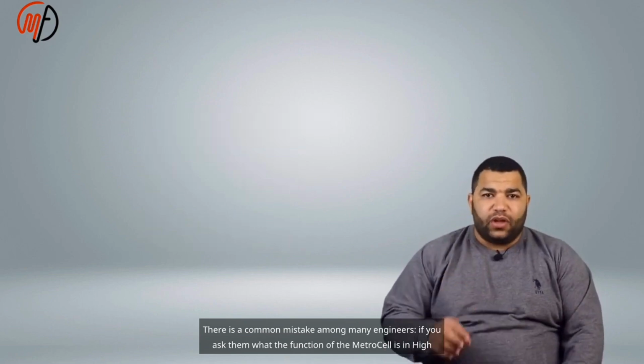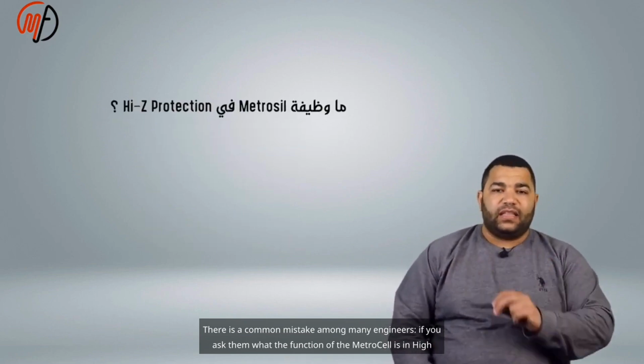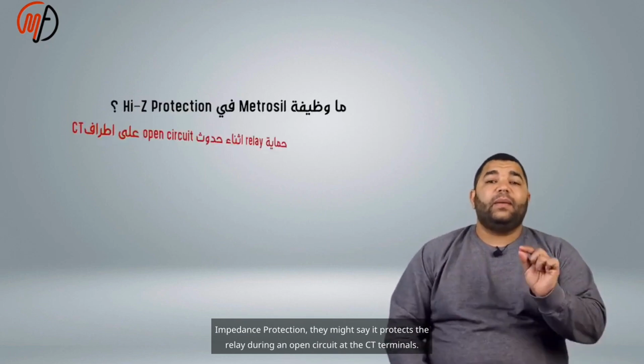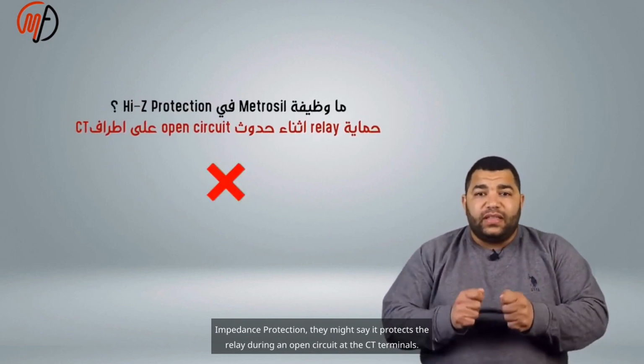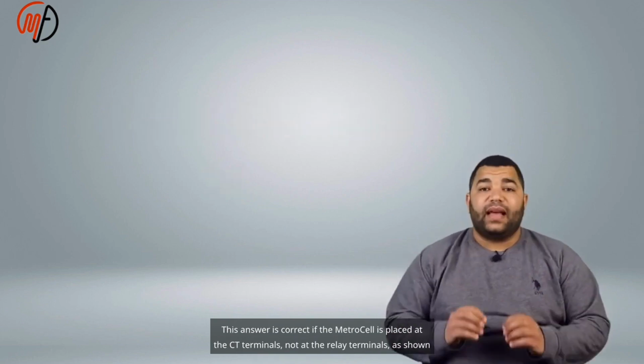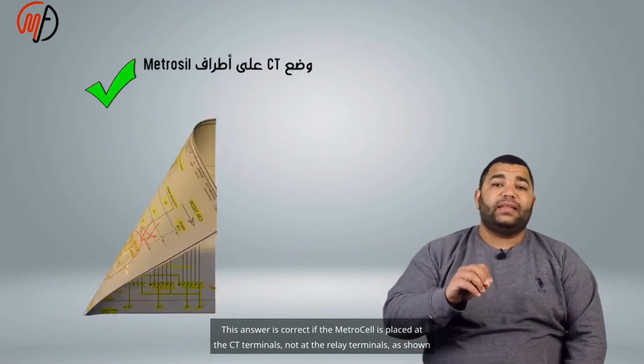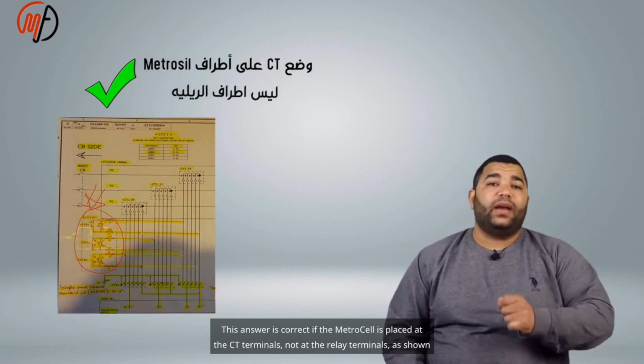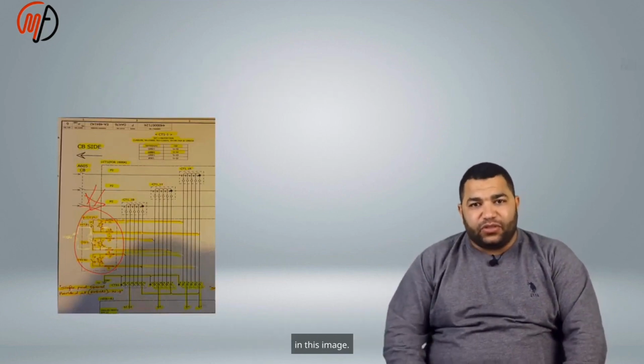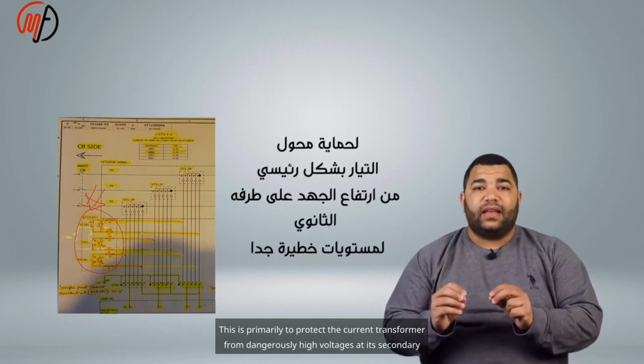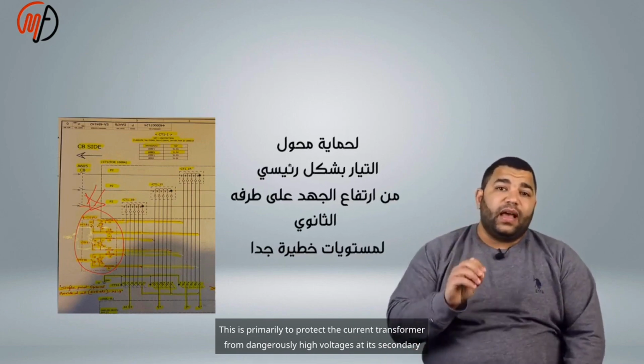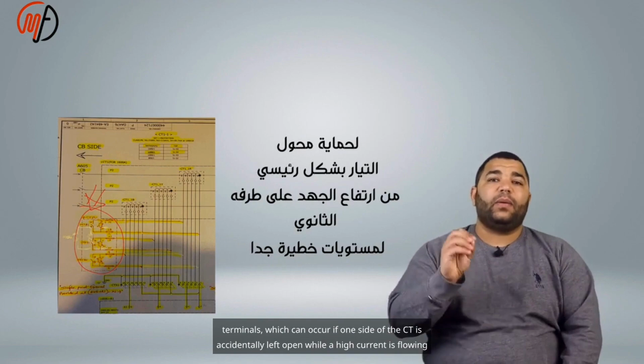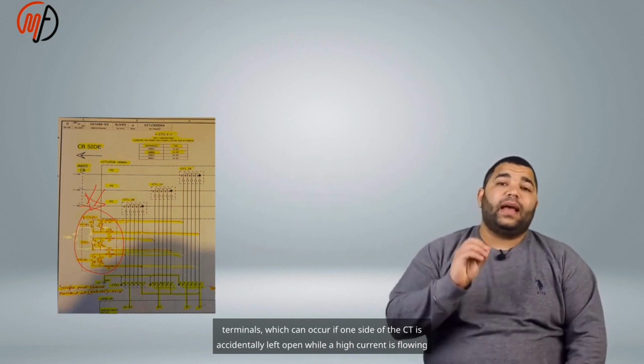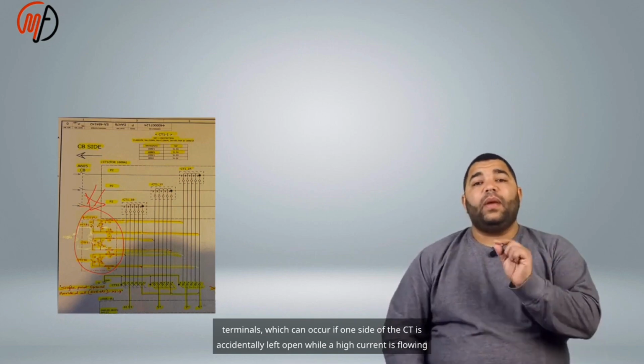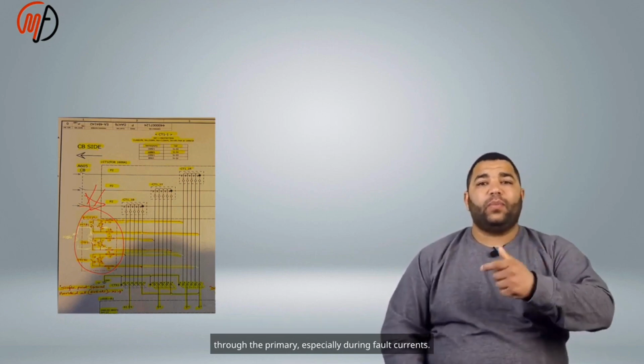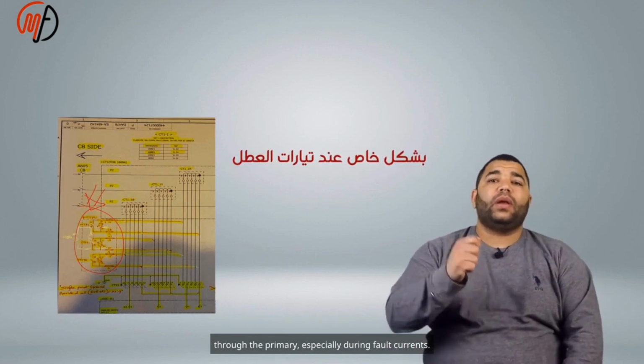If you ask them what the function of the Metrosil is in high impedance protection, they might say it protects the relay during an open circuit at the CT terminals. This answer is correct if the Metrosil is placed at the CT terminals, not at the relay terminals, as shown in this image. This is primarily to protect the current transformer from dangerously high voltages at its secondary terminals, which can occur if one side of the CT is accidentally left open while a high current is flowing through the primary, especially during fault currents.